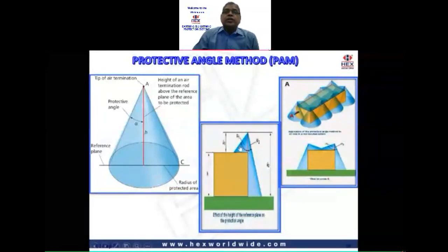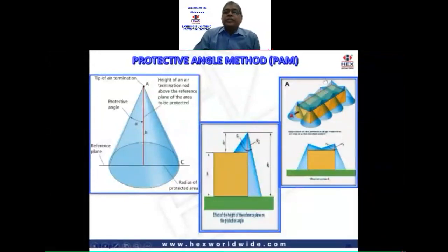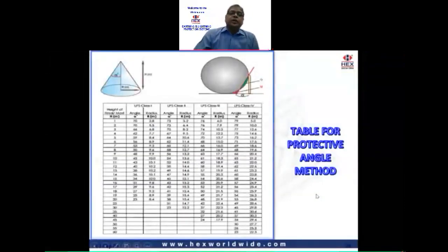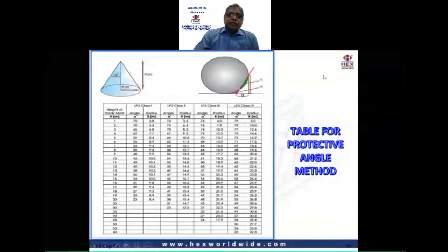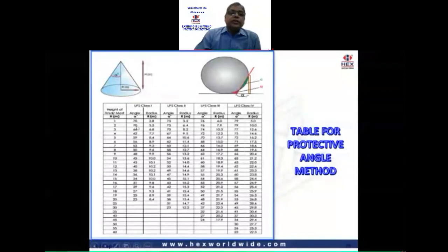Now you can see in the third figure how the representation is made graphically and how many numbers are required as per this cone of protection by using the protective angle method. This is a table that the standard gives. So for a height of 1 meter, for level one, the angle is 70 degrees. For level two, also it's 70 degrees. Sorry, for 2 meters.